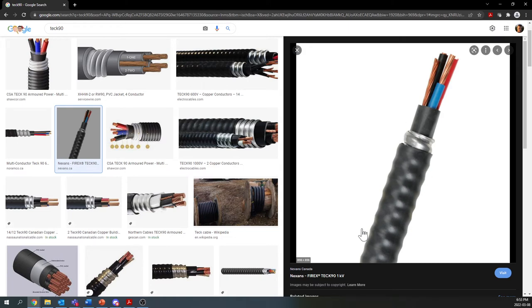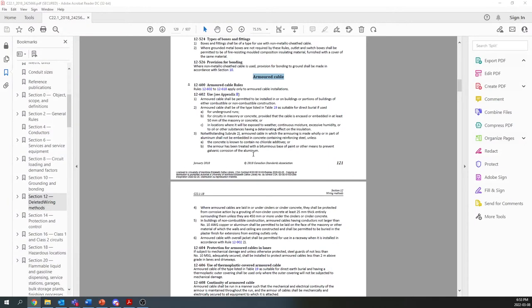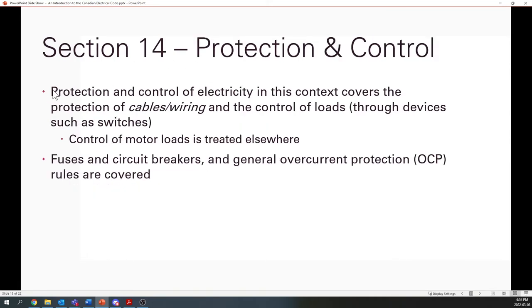This Teck cable can be used in a super wide range of situations. It can be used where it's subject to mechanical damage, underground, underwater even, in hazardous locations, all kinds of good stuff. So it's super useful to have around if you need to install some wire. So that's section 12. Protection and control is section 14. This covers how to use circuit breakers, fuses, and how to use switches to control loads.